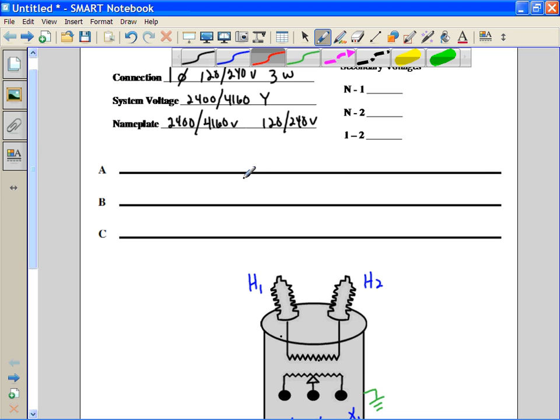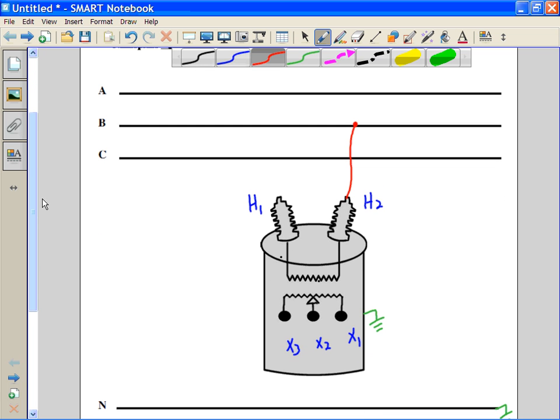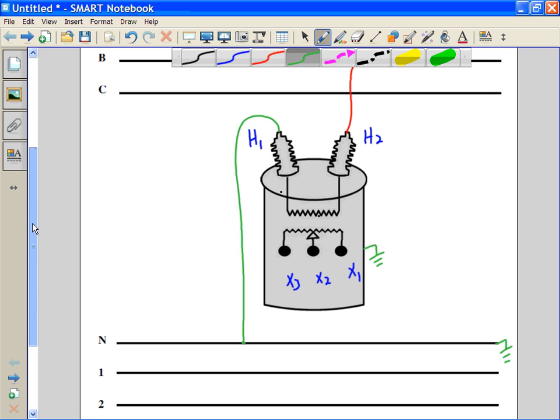And again, this is a Y connection, so a Y connection can be described as a phase to neutral connection. So I need to take one phase into one primary bushing, and the other primary bushing will be connected to the neutral. So I'm going to just take B phase this time, and I'm going to connect it into the H2 bushing. It doesn't matter which bushing you connect it to. If you have a transformer that has 2 primary bushings, you can use either one. And H1 then in this case will come down and connect to the neutral.